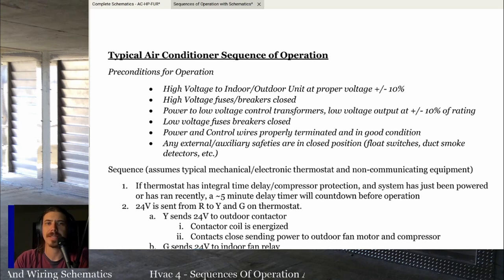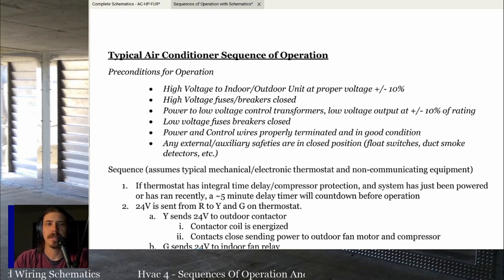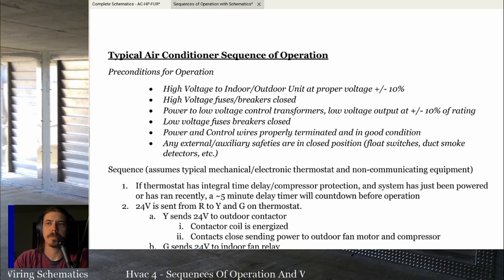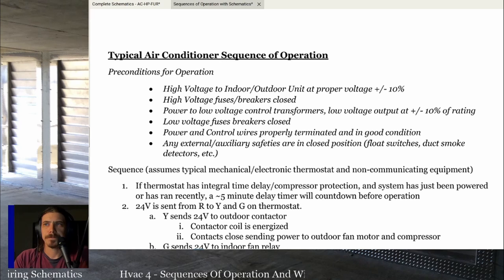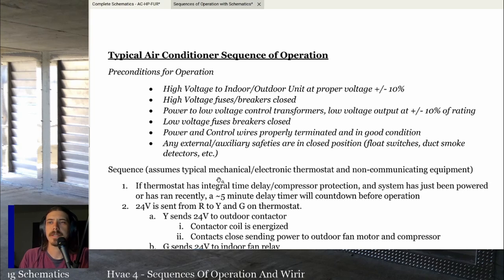Your low voltage fuses and breakers need to be closed, your power and control wires have to be properly terminated and in good condition, and any external or auxiliary safeties need to be in the closed position. When we look at a sequence of operation, it's not going to include things people added after installation — float switches, duct smoke detectors, EasyTrap switches, whatever the case may be. If those are in the open position cutting off power to your thermostat or your outdoor contactor's yellow wire, things aren't going to operate.